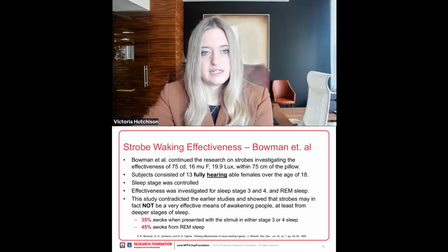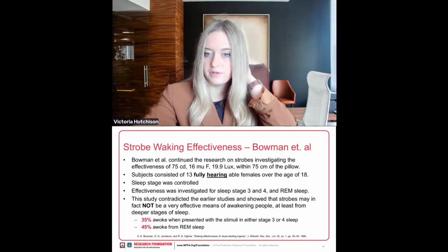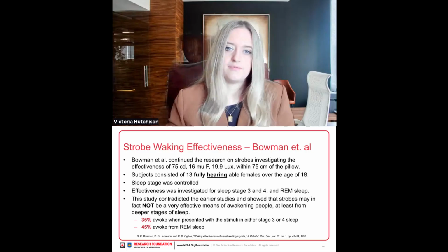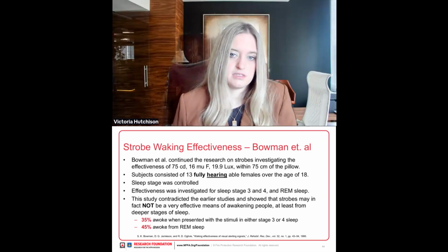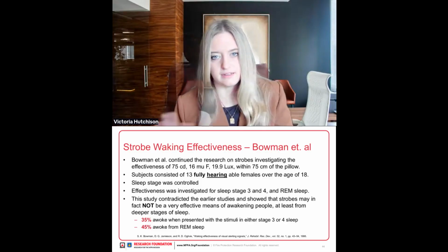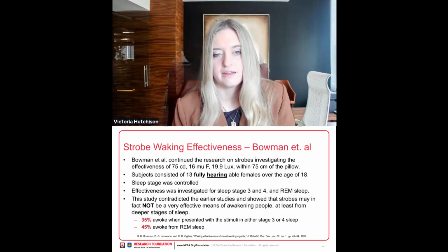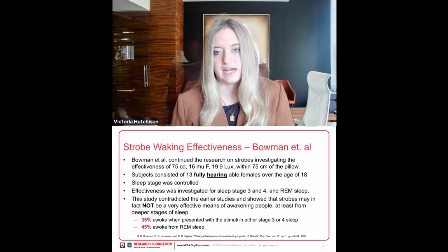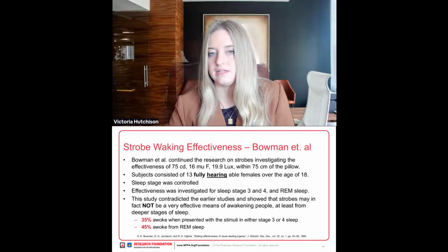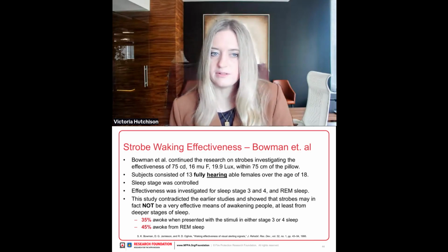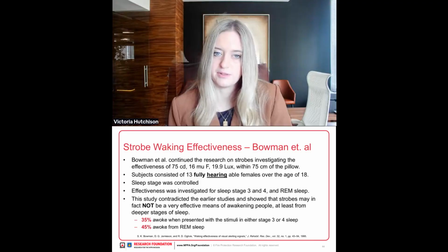Strobe waking effectiveness here from a study from Bowman. This again is an older study from 1995, but it continued the research on strobes, investigating the effectiveness of 75 candela, and you can see the different criteria there, but it was placed 75 centimeters from the pillow. So this is a factor that really plays a lot into the overall effectiveness, and those details weren't always fully available in all of the studies for comparison purposes.